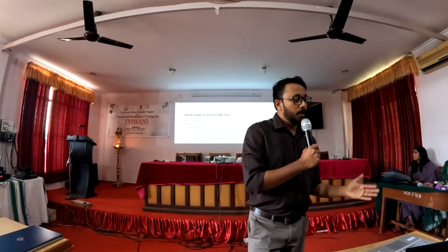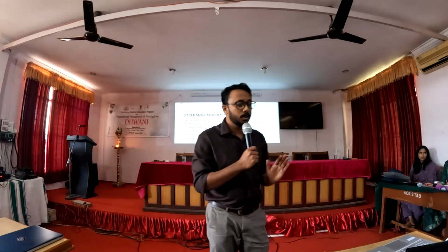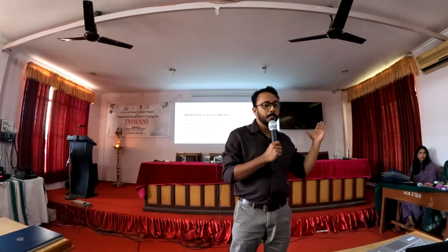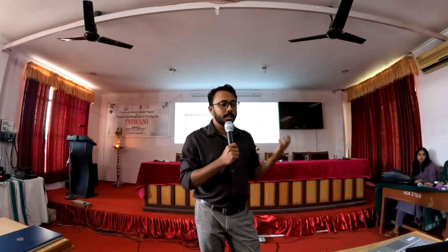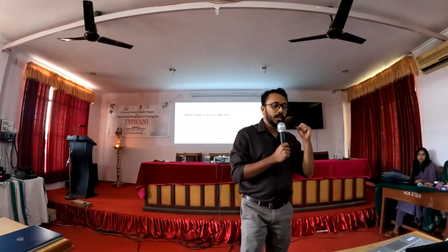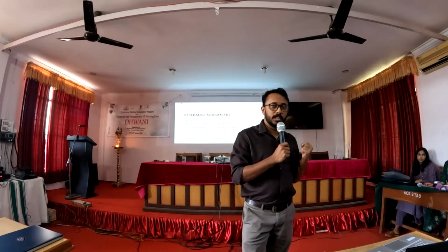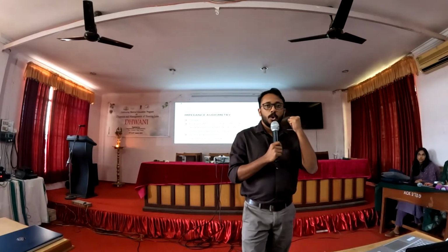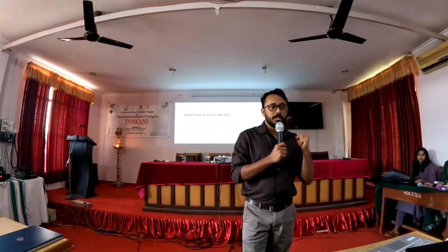Other component of audiometry is tympanometry. So tympanometry is based on the principle that when a sound strikes the tympanic membrane, some of the sound energy is absorbed and some part is reflected. A stiffer tympanic membrane will reflect more of sound energy than a compliant one. So by changing the pressure in a sealed external auditory canal, and then measuring the reflected sound energy, it is possible to find the compliance or stiffness of the tympano-ossicular system.